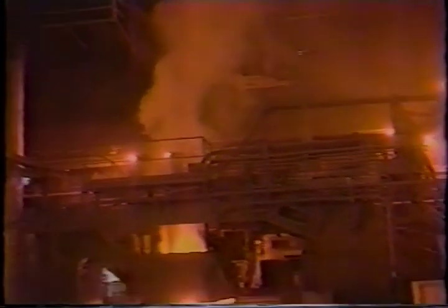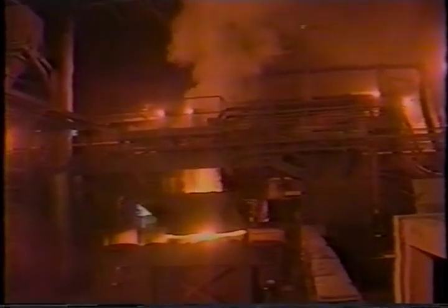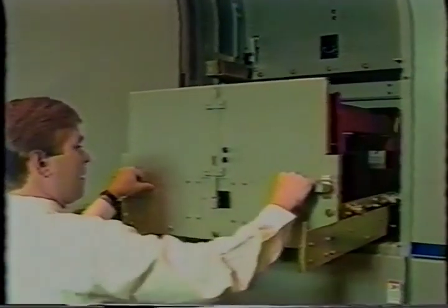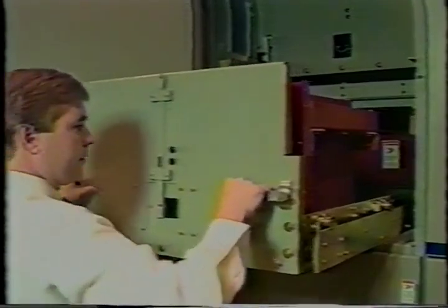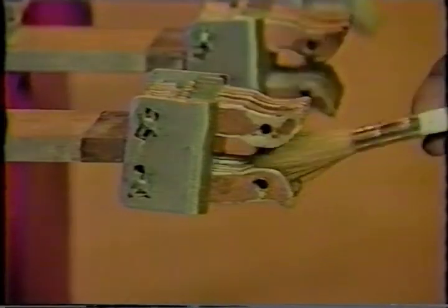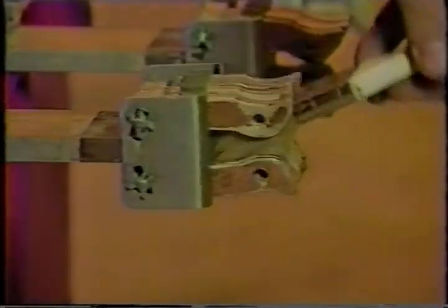Westinghouse switchgear is designed so that lubrication is not required under normal conditions. However, abnormal local conditions or severe circuit operating conditions may demand the use of lubricants. In such cases, a dry or powder lubricant should be used on moving or mating mechanical parts, and a thin film of Vaseline on disconnecting contacts. The application of the lubricants should be held to a minimum to reduce the accumulation of dust and dirt.